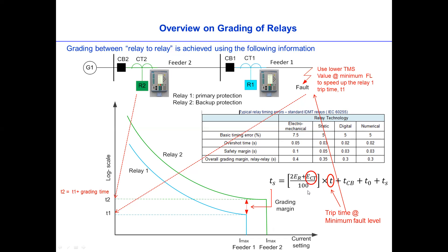Then what do we need to know about the ECT? ECT is the CT error, basically. It depends on the CT type, but normally the CT error is 5%, and since we have two CTs on here, the total CT error would be 10%.